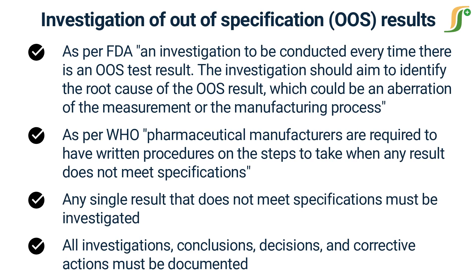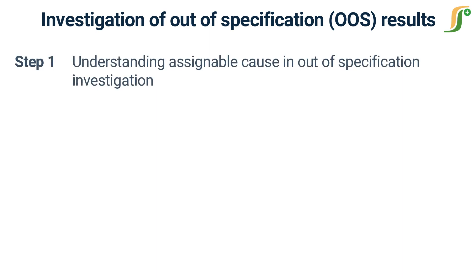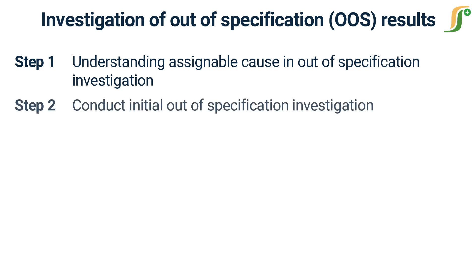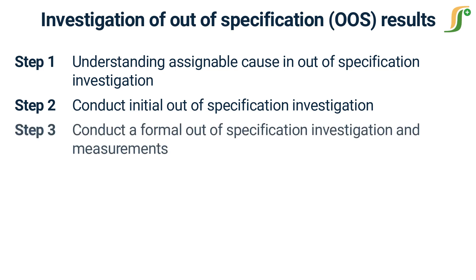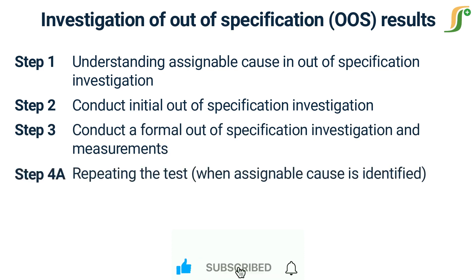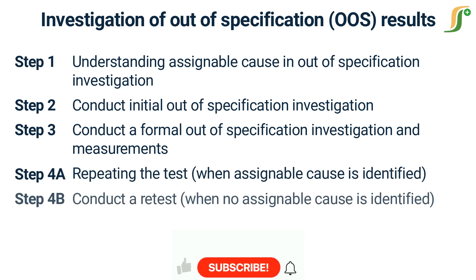Now let us understand the procedure for the investigation of OOS results. Investigation of out-of-specification results can be conducted in four steps. In the first step, we need to understand assignable cause in out-of-specification investigation. In the second step, an initial out-of-specification investigation is conducted. In the third step, a formal out-of-specification investigation and measurement is conducted. In the fourth step, if an assignable cause is identified then the test is repeated, and if no assignable cause is identified then retesting of the product is conducted.